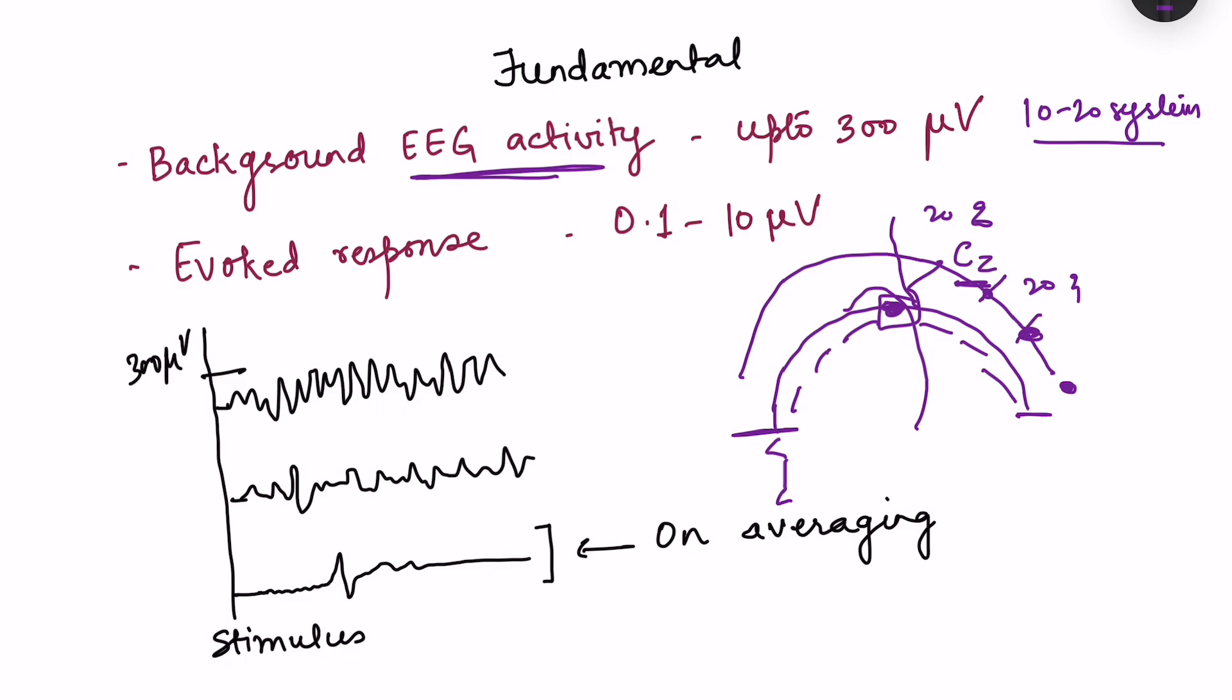When we are recording evoked response, we provide a stimulus to the person and then there is evoked response. Now the problem is that the background EEG activity is up to 300 microvolt in amplitude. However, evoked response is very small, it is only 0.1 to 10 microvolts. That means that if this is the routine EEG activity from the brain being recorded, then even if you are giving the stimulus, evoked response will somewhere be in between and we will not be able to identify which is the evoked response.